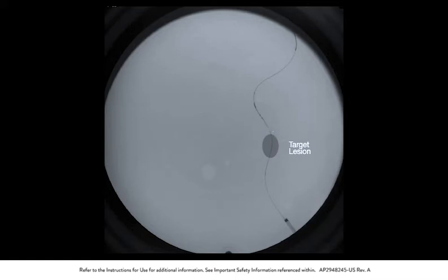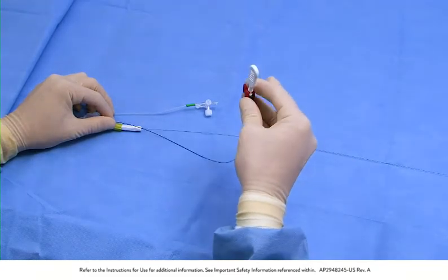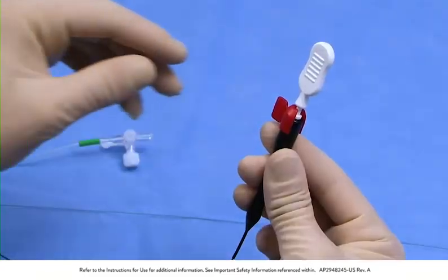Once the delivery catheter is positioned, the filtration element may be deployed. Remove the red locking clip from the black handle of the delivery catheter.